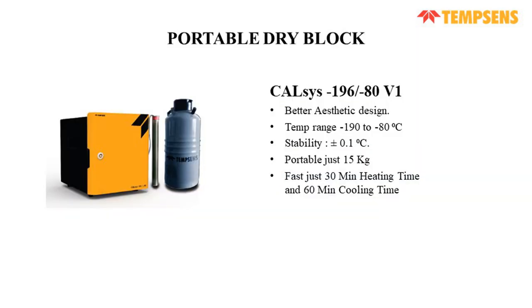So this is the portable dry block model. The temperature range for this one is minus 196 degrees to minus 80 degrees. The stability is plus minus 0.1, and the weight is just 15 kg. It has just 30 minutes heating time and 60 minutes cooling time. It cools down to minus 190 degrees in just 60 minutes from the ambient.